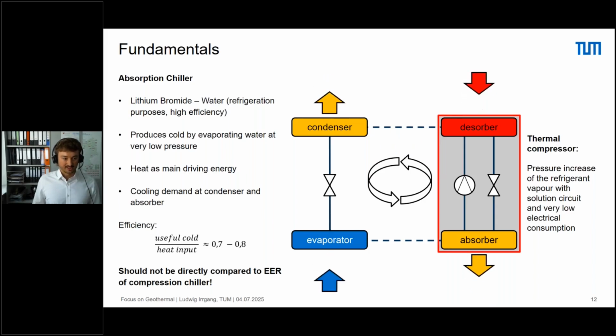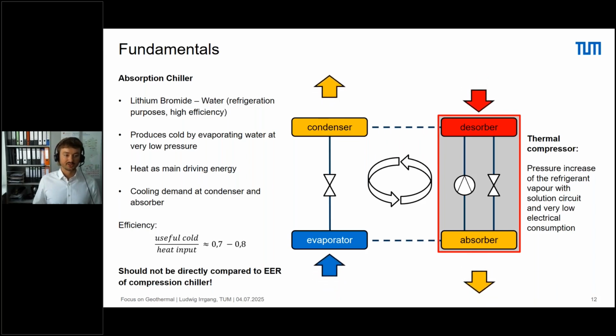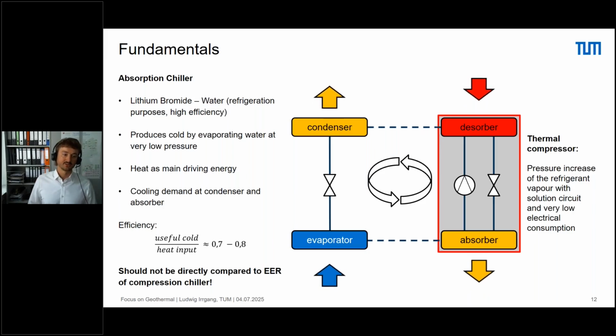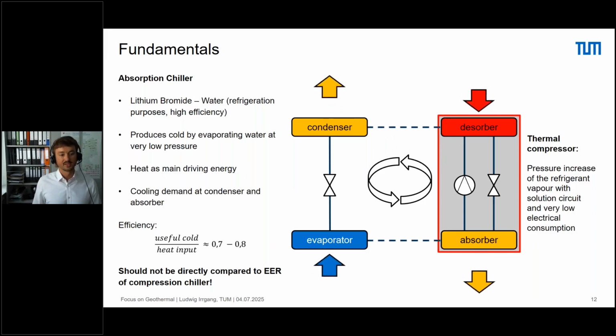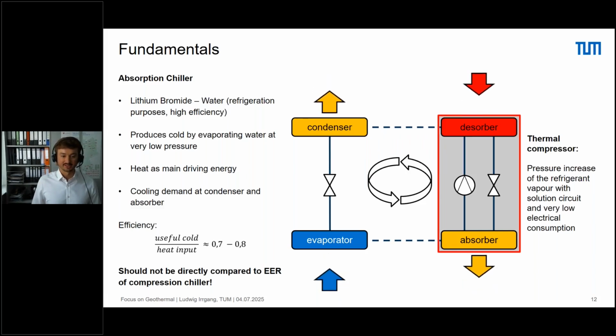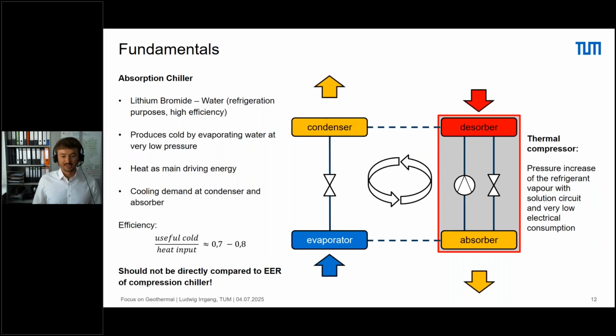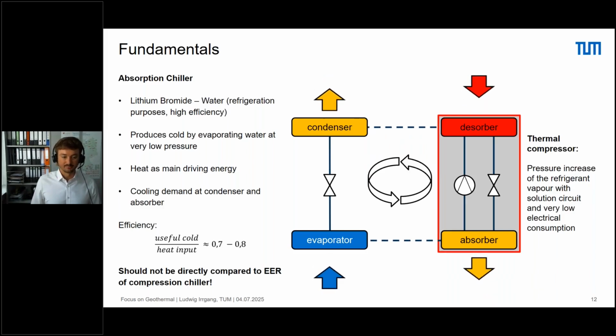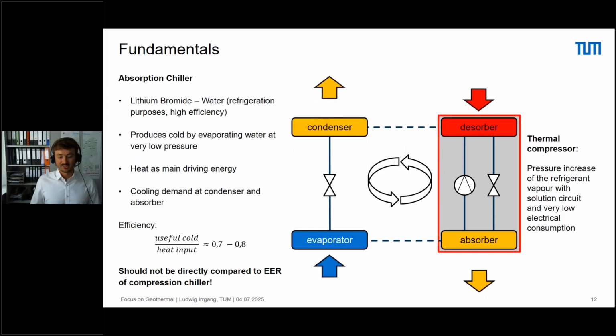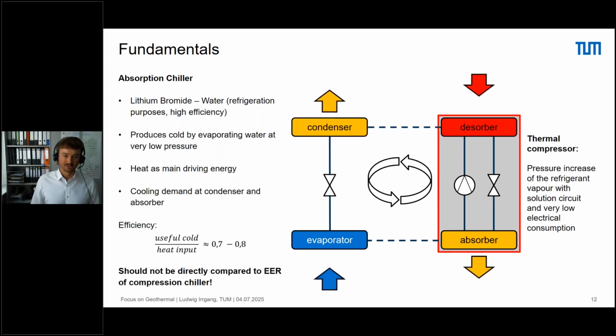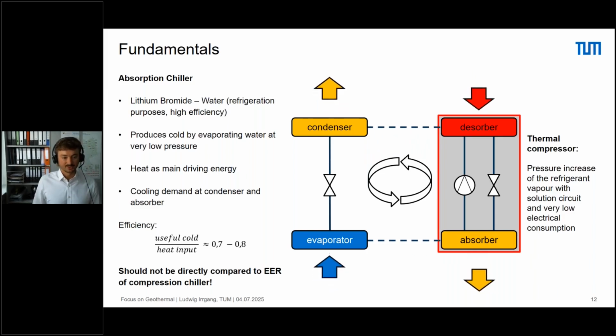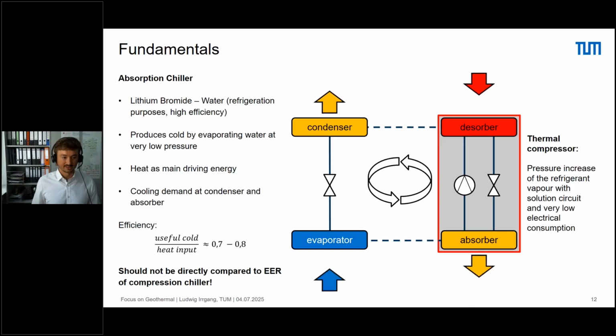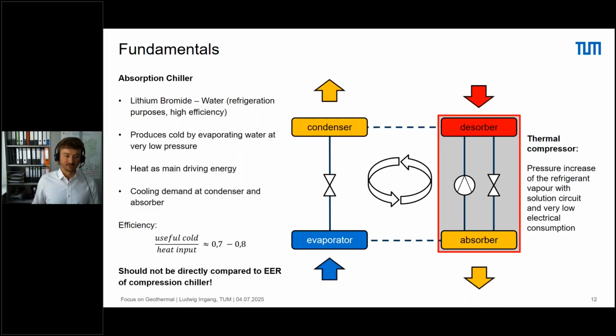The efficiency of the whole cycle is usually measured as the useful cold output in the evaporator in comparison to the heat input at the desorber, and it's usually around 0.7 to 0.8. I want to note that you should not compare that directly to the EER of a compression chiller, because that would give the absorption chiller an unfair disadvantage. What we use here as input is heat, or maybe even low temperature heat. And on the other hand, the compression chiller uses electrical energy, which is pure exergy. So we should never compare the EER directly to the COP, and we will later see how one translates into another.